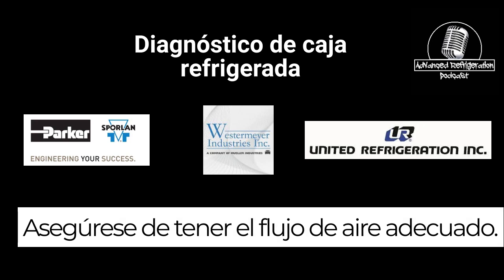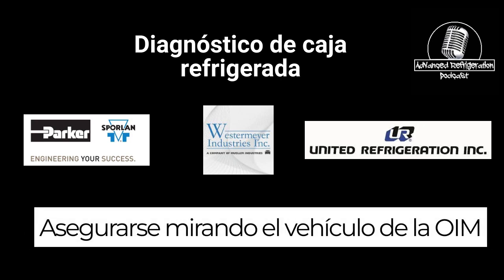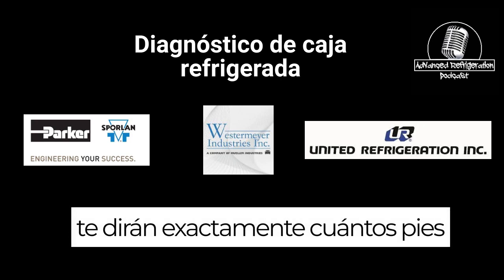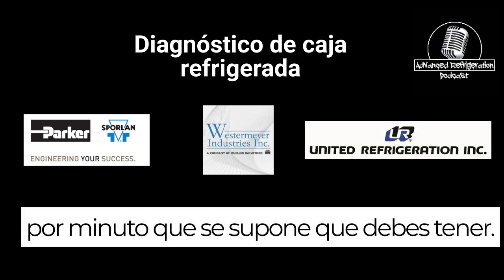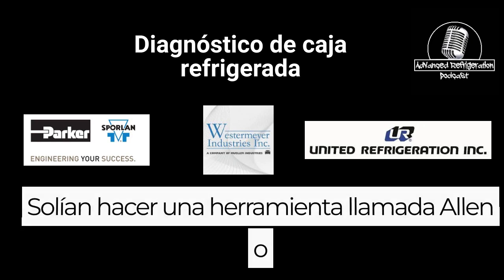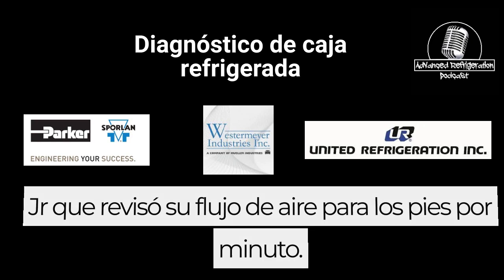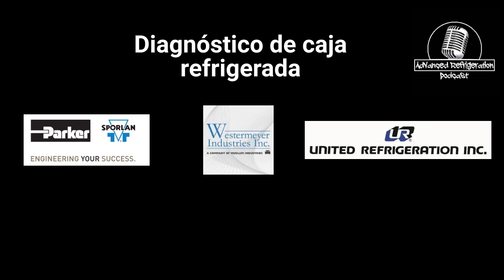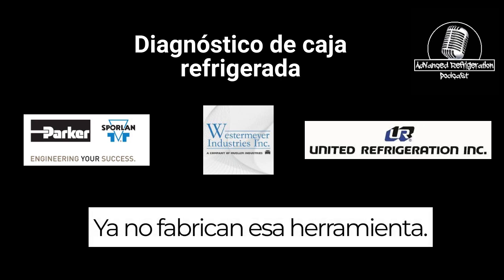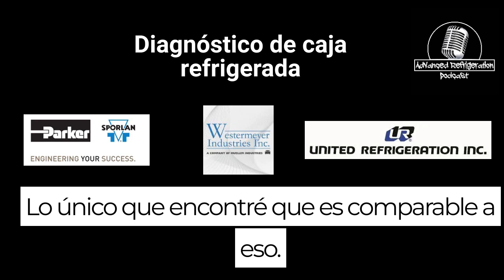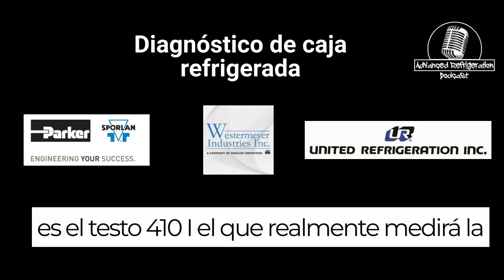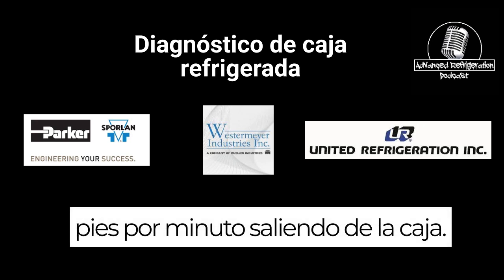Make sure you have proper airflow. By looking at the IOM manual, they will tell you exactly how many feet per minute you're supposed to have. They used to make a tool called an Alnor Junior that checked your airflow in feet per minute. They no longer make that tool. The only thing I found that's comparable is the Testo 410i. That will actually measure the feet per minute coming out of the case.